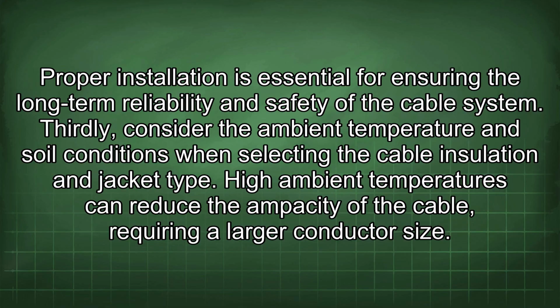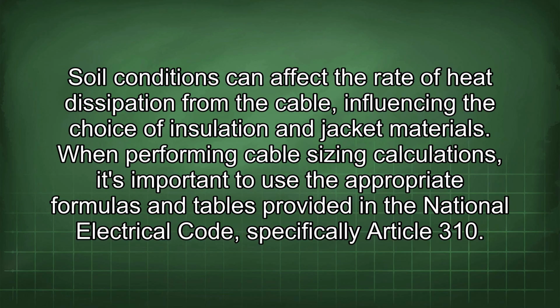Thirdly, consider the ambient temperature and soil conditions when selecting the cable insulation and jacket type. High ambient temperatures can reduce the ampacity of the cable, requiring a larger conductor size. Soil conditions can affect the rate of heat dissipation from the cable, influencing the choice of insulation and jacket materials.